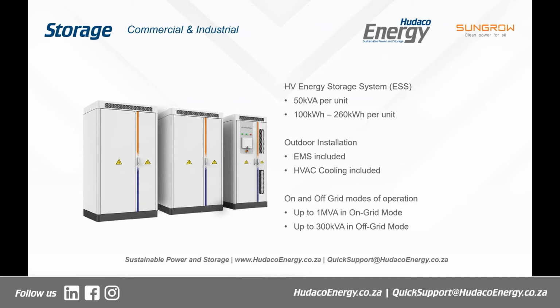It is designed to operate seamlessly with the string inverters as well in an AC coupled mode. So in other words, on your main AC box, you would have your energy storage system connected. You would also have your AC coupled PV system connected, and the EMS from Sungrow will take control not only of the PV system, telling the inverters what to do, but it will also interface with the generator controller, if you have one on site, for example, Deep Sea, and it will take control of the entire site, as well as push all of that data through to iSolar Cloud, where you can view everything that's happening remotely. This product itself is absolutely spectacular, and let's talk about how we would build it.